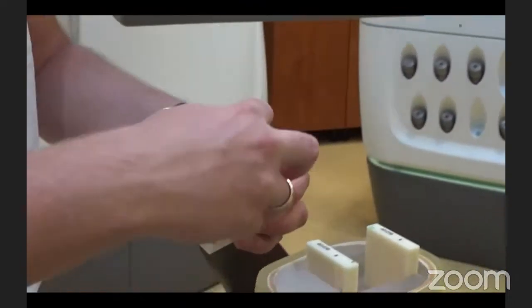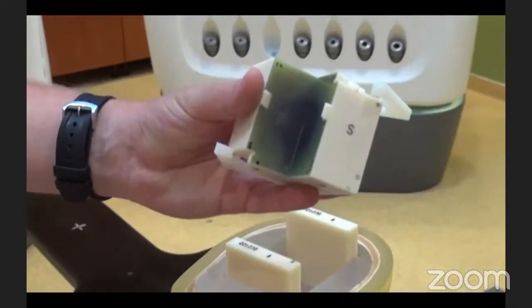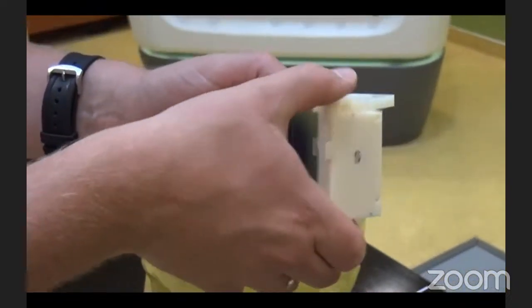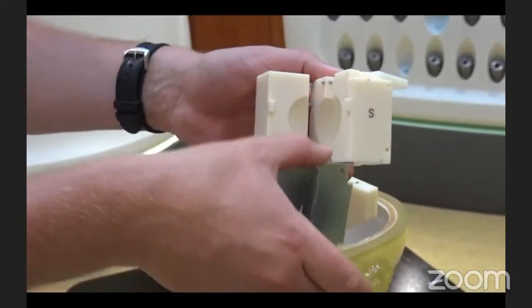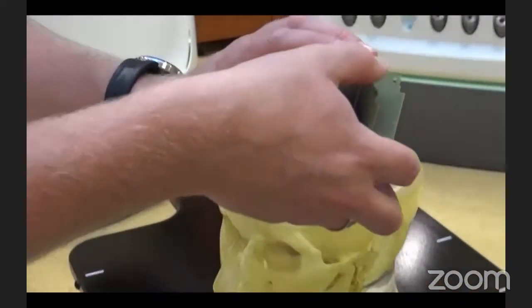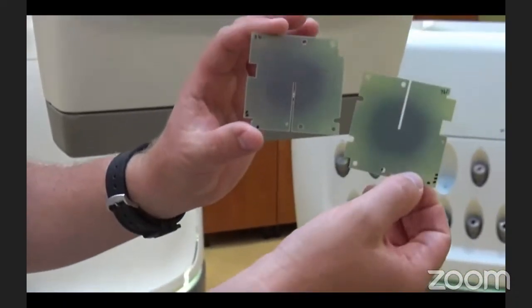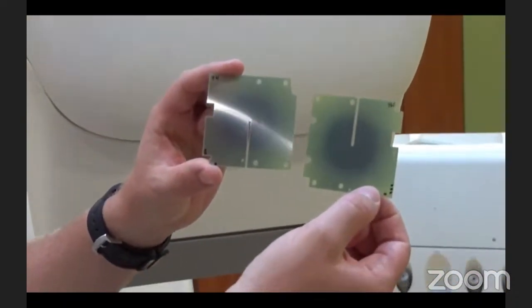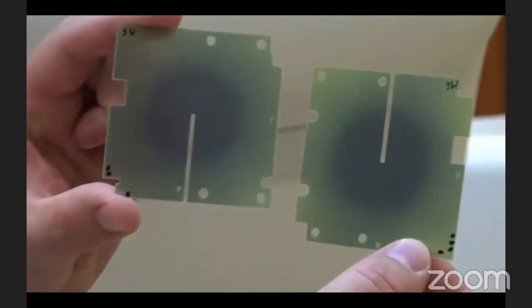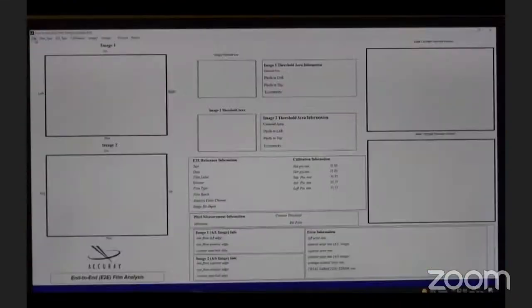The results of the end-to-end test can be seen on these GafChromic films. It will be evaluated by the software how precisely we can hit the middle of the ball cube insert. We will evaluate the 70% isodose level on these films. For end-to-end tests, we load the image pair, the film pair, and one background film in one scan.